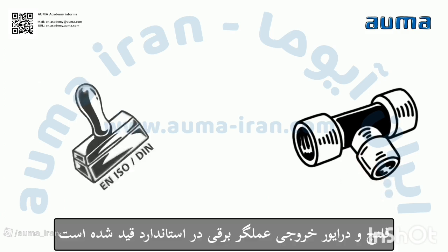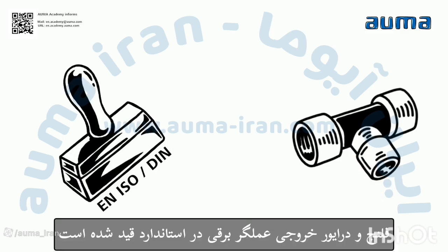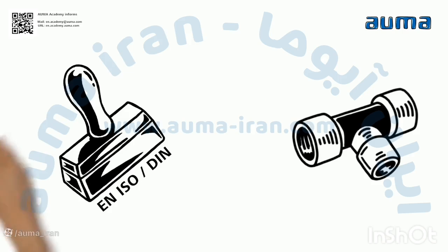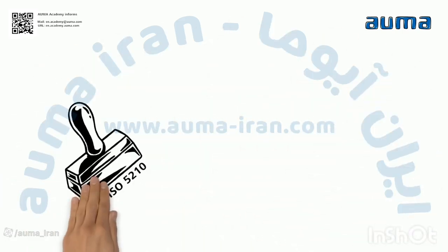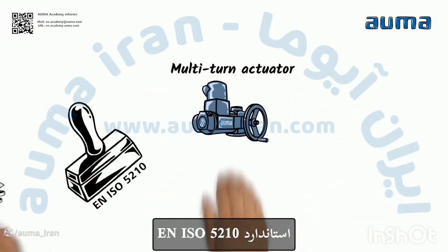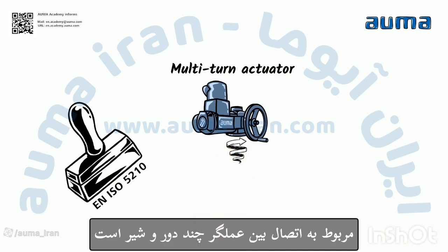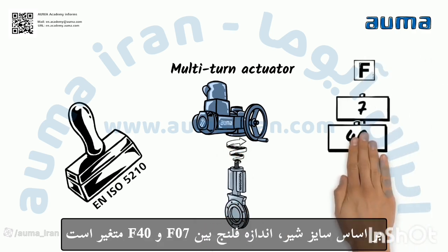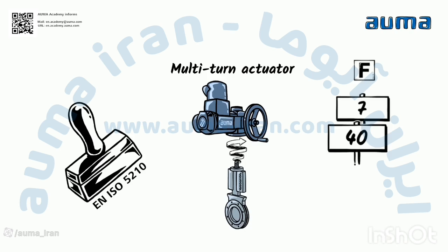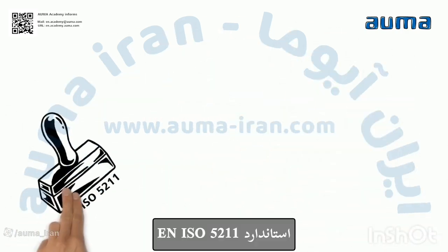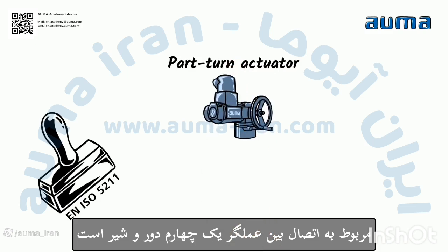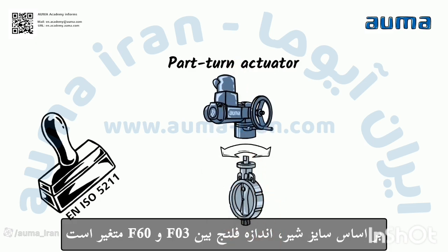The flange and the output drives are standardized. EN ISO 5210 standard applies to the connection between multi-turn actuators and valves. The flange varies between F07 and F40, depending on the valve size. EN ISO 5211 standard applies to the connection between part-turn actuators and valves. The flange varies between F03 and F60.